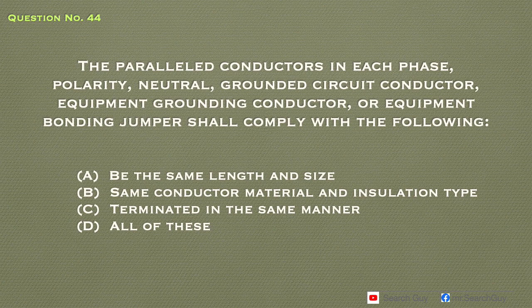Question number 44. The parallel conductors in each phase, polarity, neutral, grounded circuit conductor, equipment grounding conductor, or equipment bonding jumper shall comply with the following. A. Be the same length and size, B. Same conductor material and insulation type, C. Terminated in the same manner, D. All of these. Answer: D. All of these.